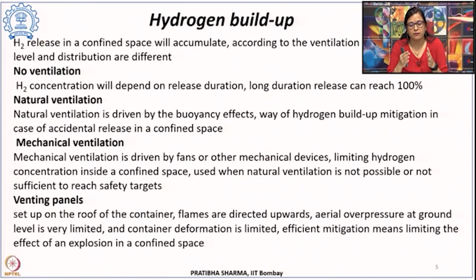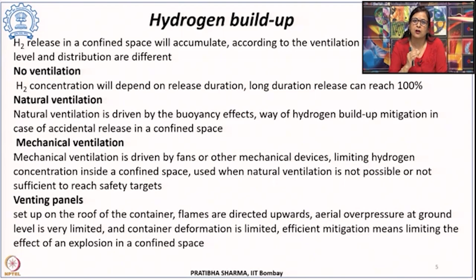However, the overpressure created by this ignition or explosion can be reduced by the venting panels, so that the flames are directed upwards, the overpressure at ground level is limited, and the container deformation could be limited. Again, this is a very efficient mitigation method which could limit the after effects of an explosion in a confined space.